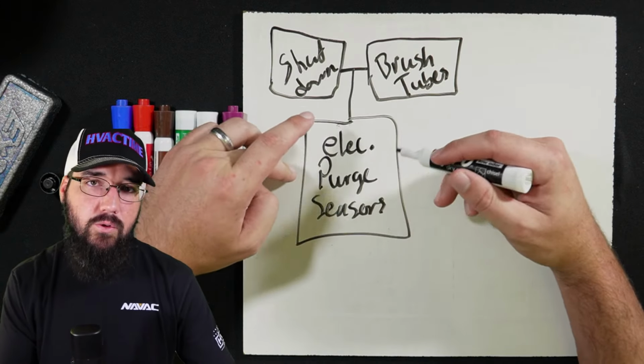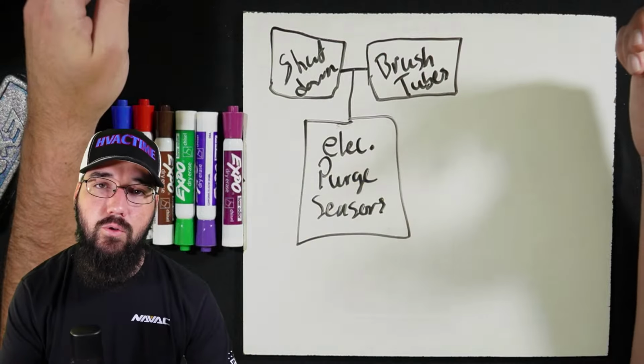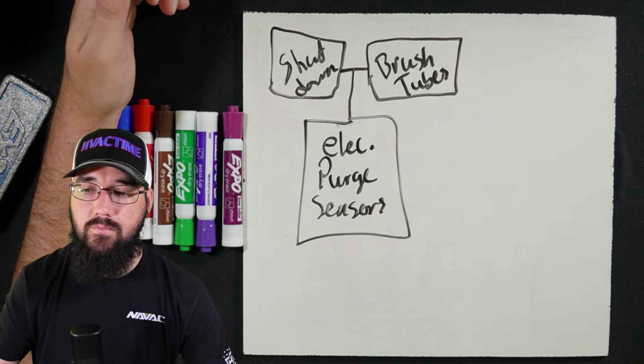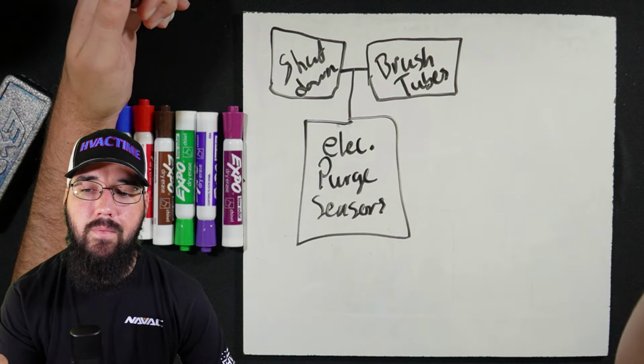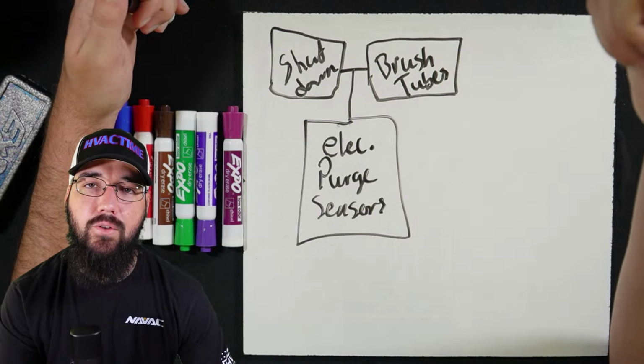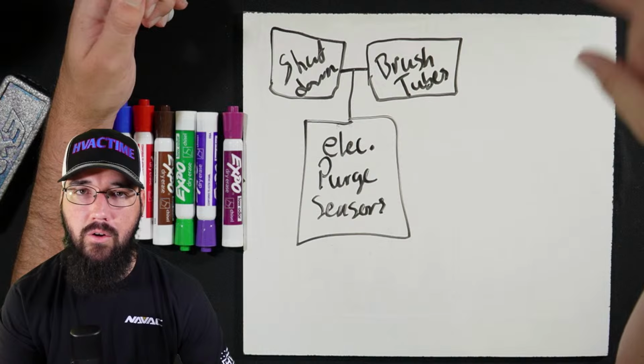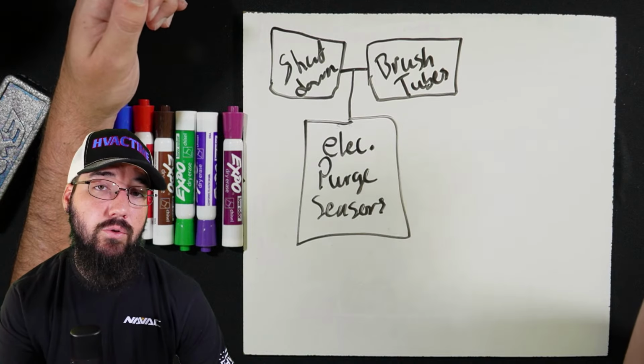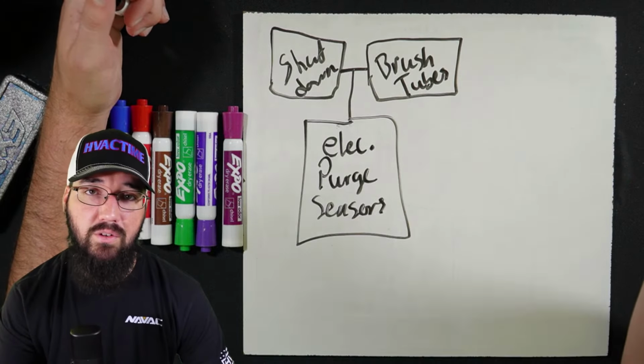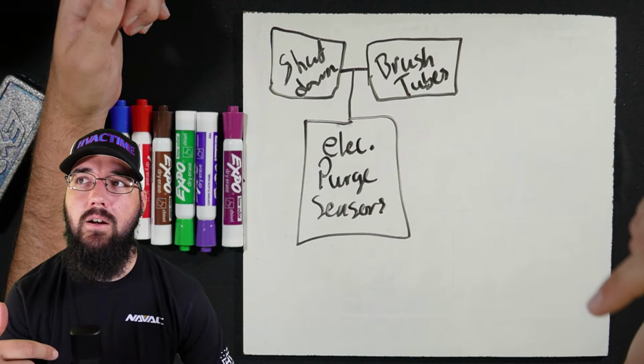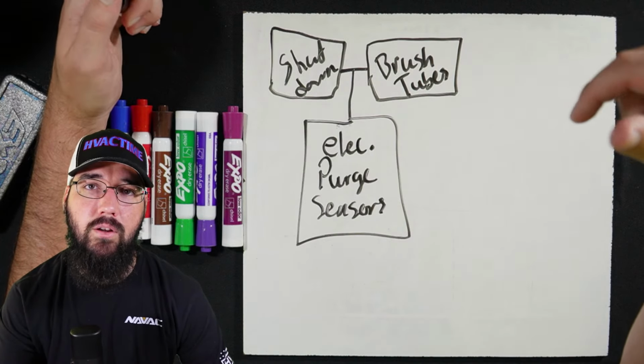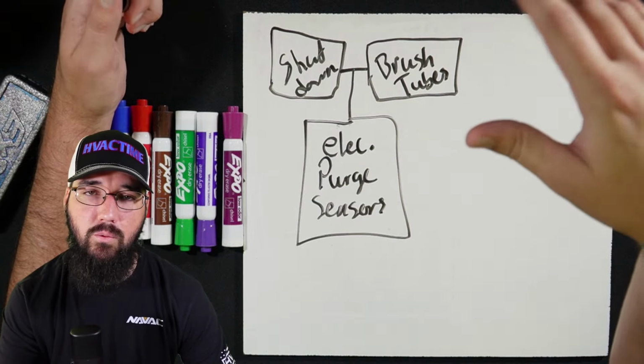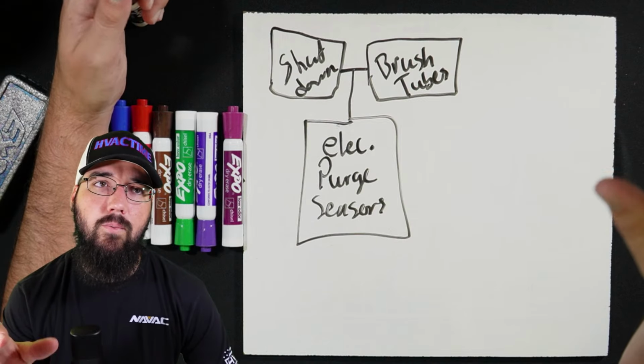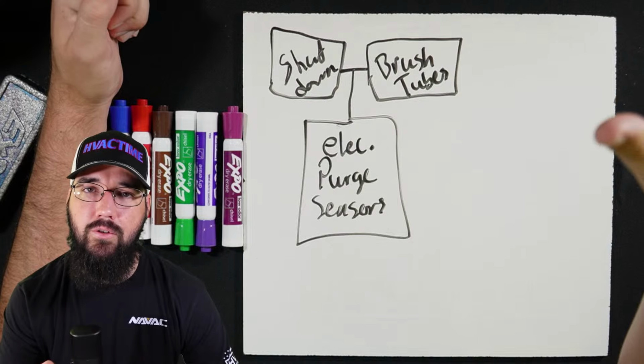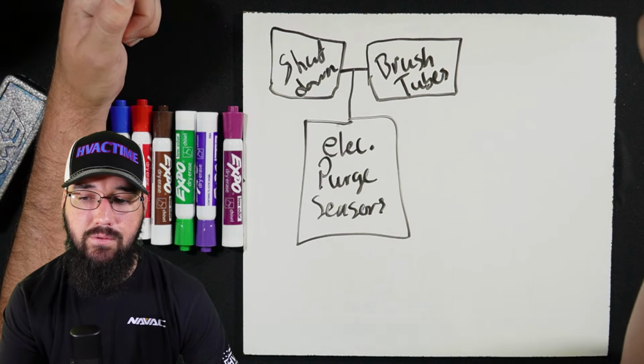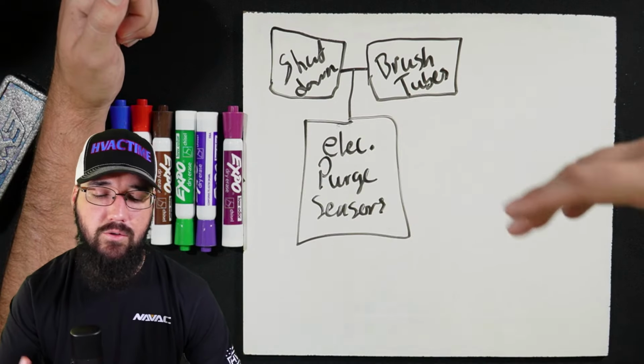All right, so one tech's on the electrical. When I say electrical, what I mean is going into the control cabinet, tightening all the electrical, and making sure that we don't have any burnt wires, we don't have anything loose. All the connections are good and tight. We're happy with everything. Then going into the drive and starter panel, whatever the case may be, servicing the starters, servicing all the connections. With a low pressure, you're not going to be megging the motor at this point. You're still in a vacuum. You have to wait until you do the pressurization for that. So yeah, cleaning the starter contacts, making sure the starters are in good shape, all the major electricals in good shape. If we have a drive system, going in and servicing the drive, again, doing any checks we need.